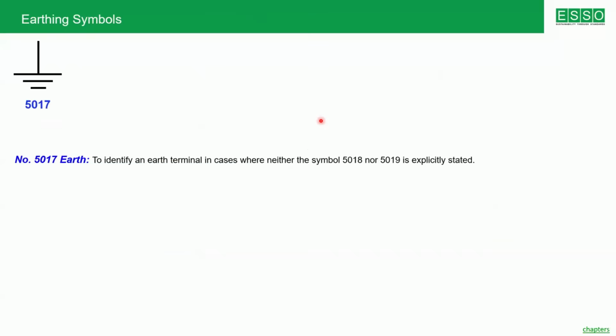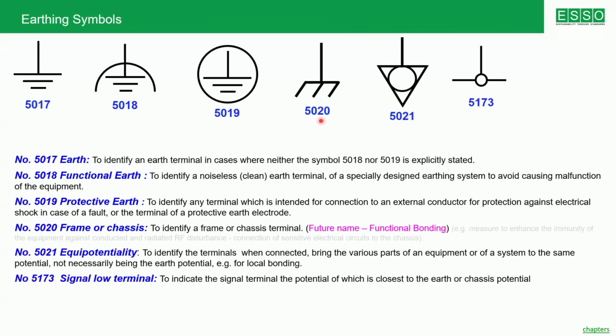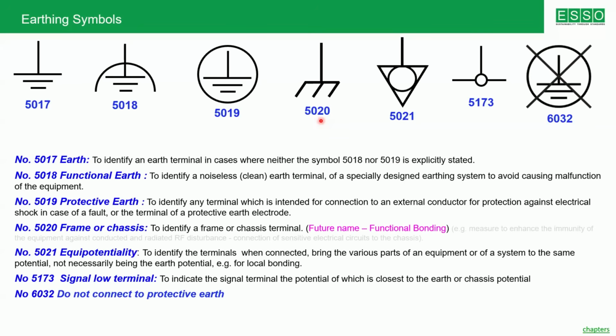So what I wanted to explain is that each of these biomedical equipment requires a different type of earthing requirement, which is very well explained in the necessary standard, the biomedical equipment standard, which is IEC 60601, but there are several associated standards. And if you look at the marking on this equipment, there are different types of markings included. The first one, 5017, is the generic symbol which we use to identify earthing. This is a symbol which has to be put on equipment to identify an earth terminal in cases where neither the symbol 5018 nor 5019 is explicitly stated. So this is for a certain purpose.